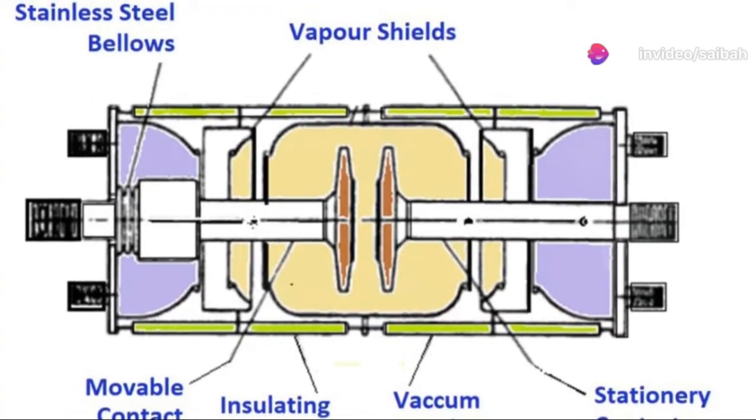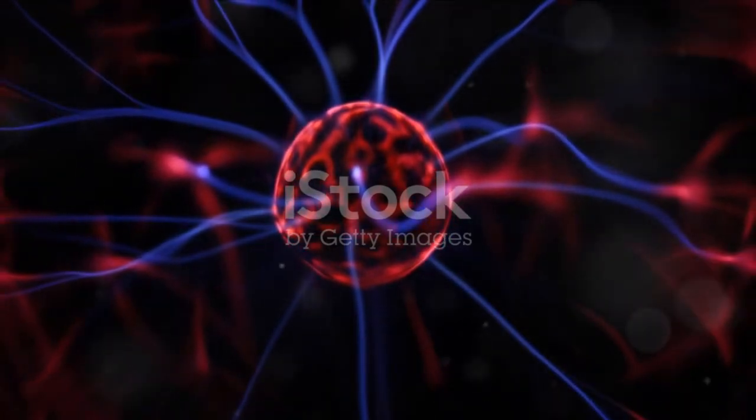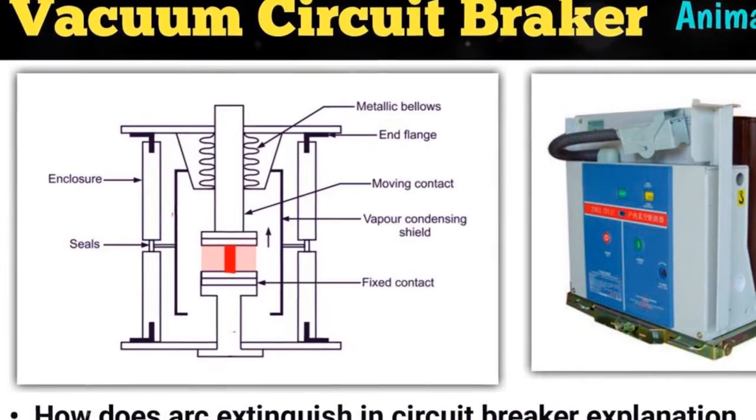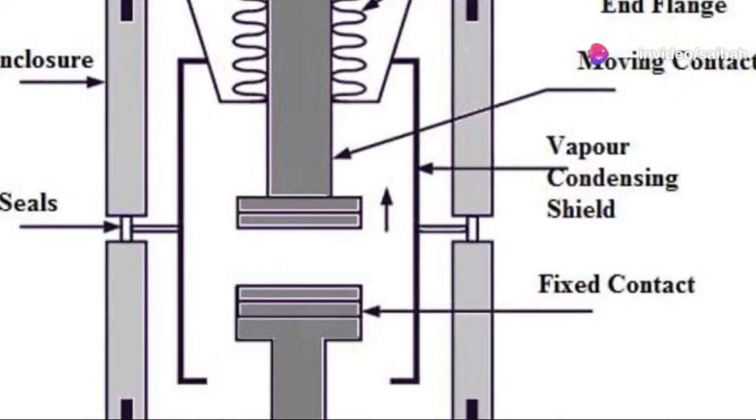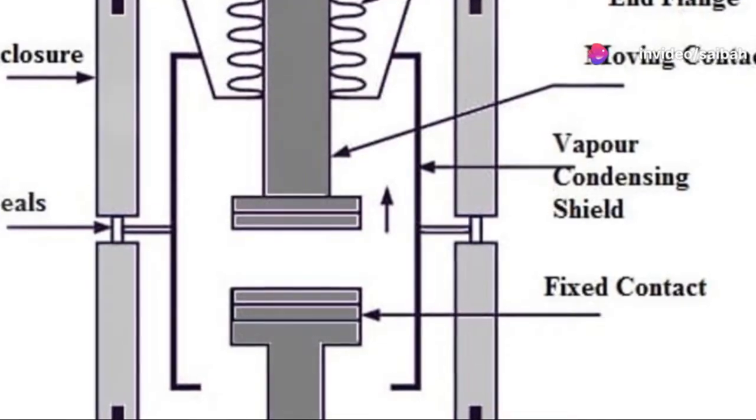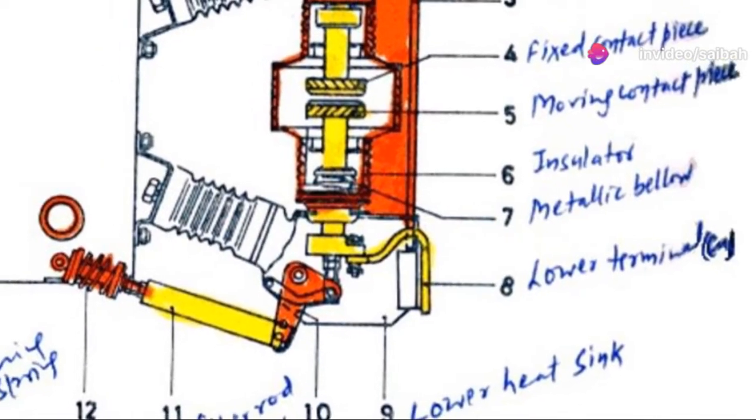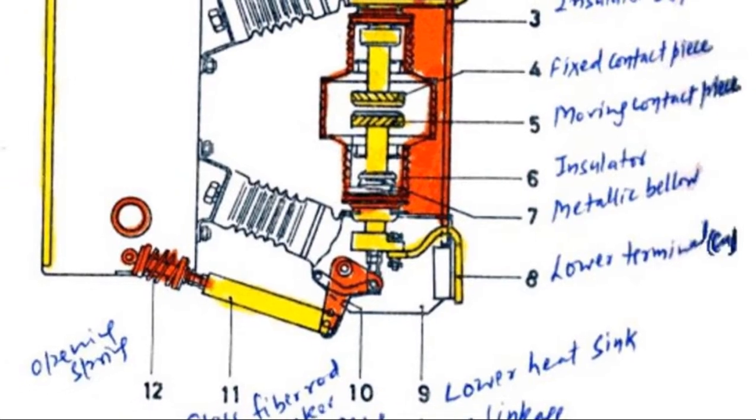Let's talk about the principle of operation. When the contacts inside a VCB separate, an arc forms. This happens due to ionization between the gap. But here's where the magic happens. In a VCB, this arc is quickly extinguished thanks to the high vacuum environment, which rapidly recovers its dielectric strength once the arc goes out.